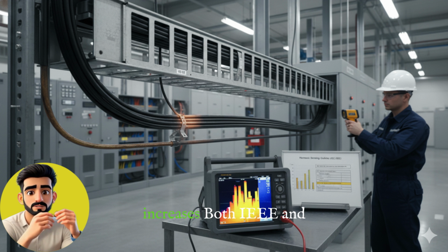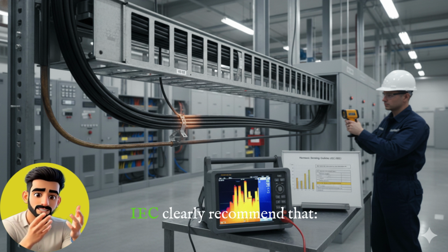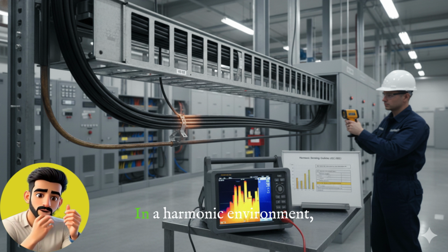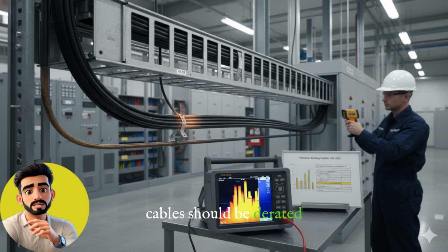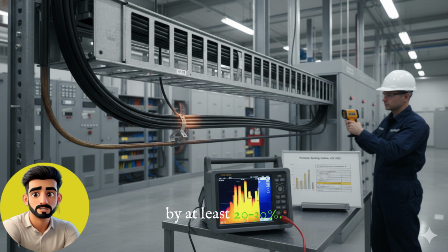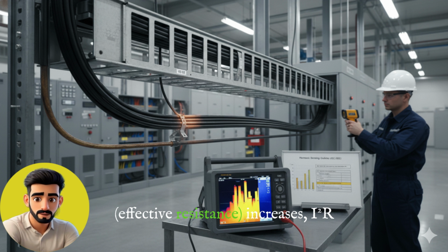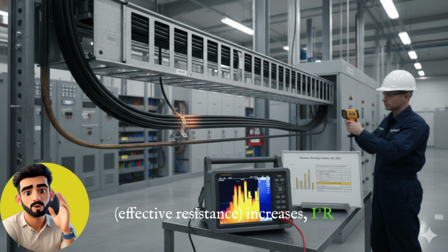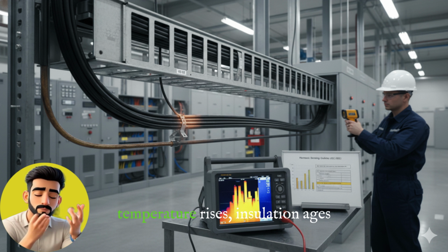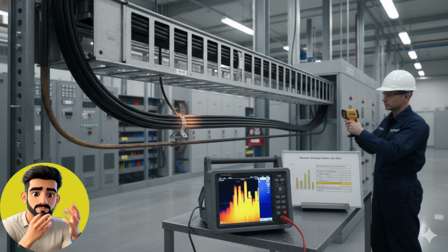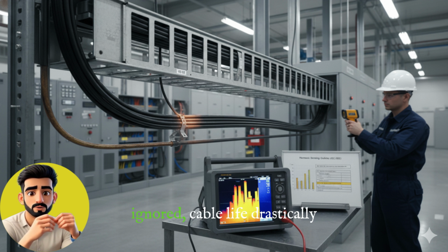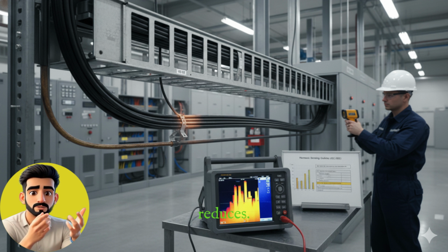3. Cable derating factor increases. Both IEEE and IEC clearly recommend that in a harmonic environment, cables should be derated by at least 20 to 30%. Because with harmonics, R, the effective resistance, increases, I squared R losses are higher, sheath temperature rises, and insulation ages faster. If derating is ignored, cable life drastically reduces.